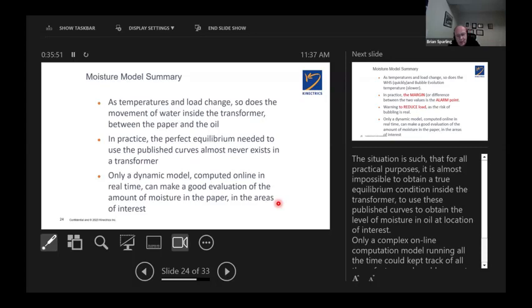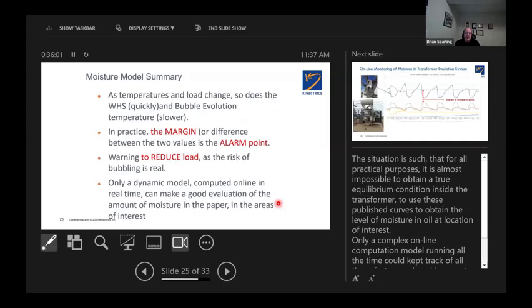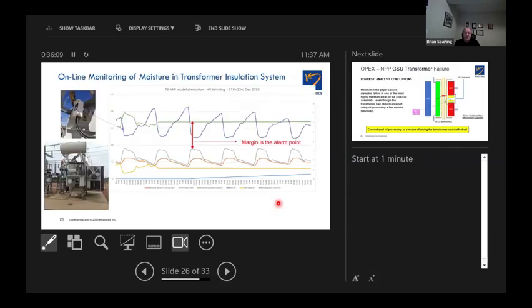In practice, perfect equilibrium never exists, but by dynamically monitoring it over time, you can derive that magic point in time when equilibrium occurs. Now, from this, we can determine the bubble evolution, an alarm point, and I'll come to that here. Here we have a transformer connected to a solar farm out in the outback of Australia. And what we're seeing here is the moisture in oil sensor and hydrogen sensor. The monitoring system is attached on the other side of the transformer. We're monitoring everything on this transformer.